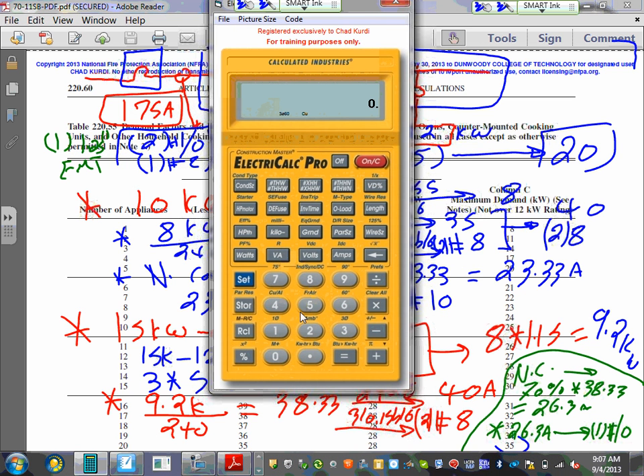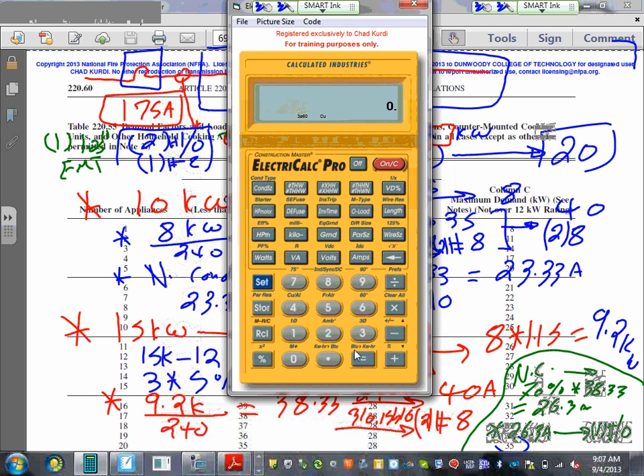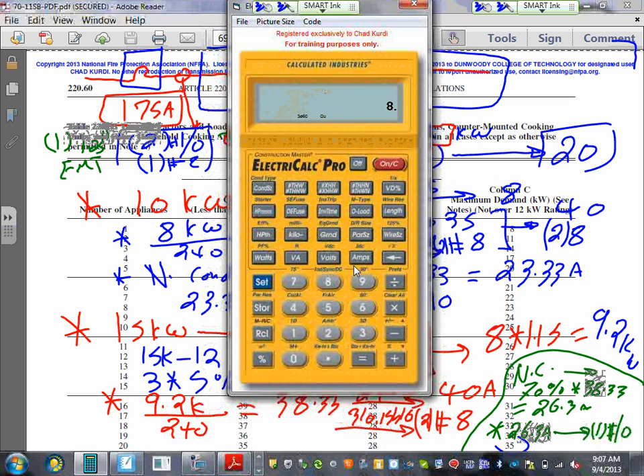So we're putting it in a pipe. We don't have to put it in a pipe. You could have bought an NM cable and wire with it, or an AC cable and wire with it, and done. But let's just say if we're going to wire it in a pipe, what was the size? I have number 8 wire size. How many conductors? I have 2 conductors, THHN.